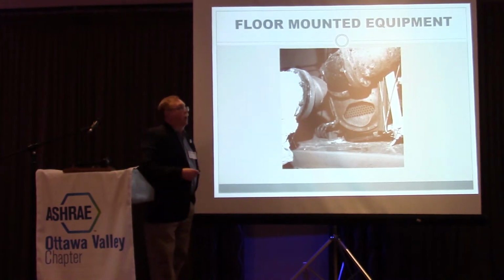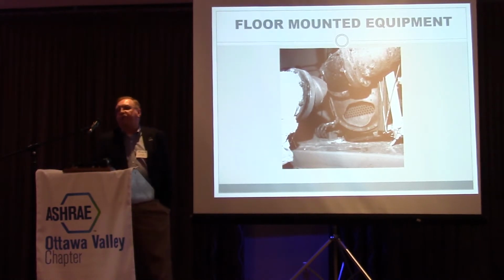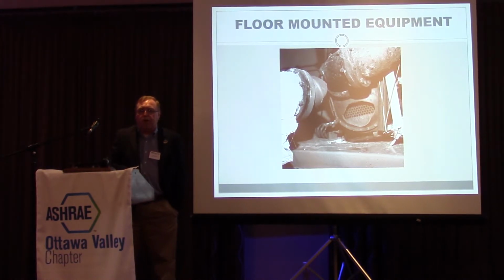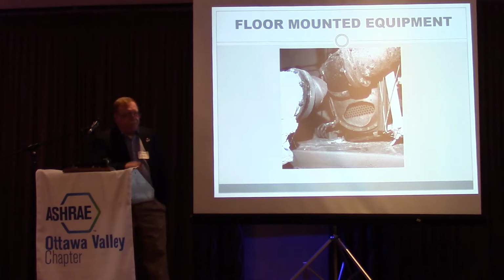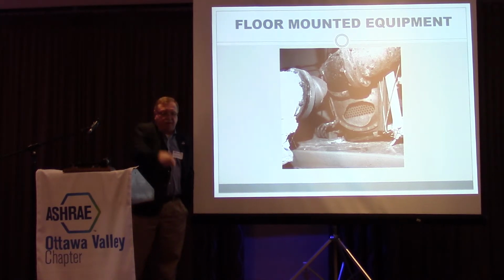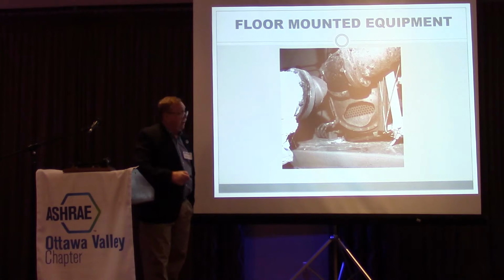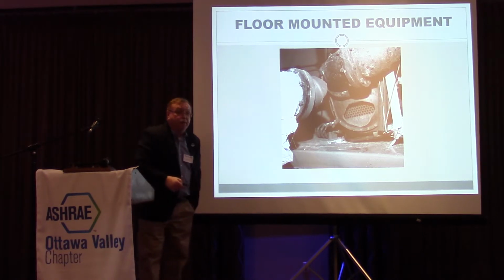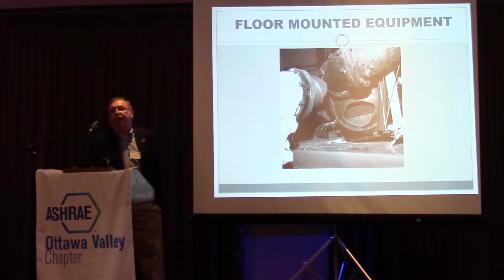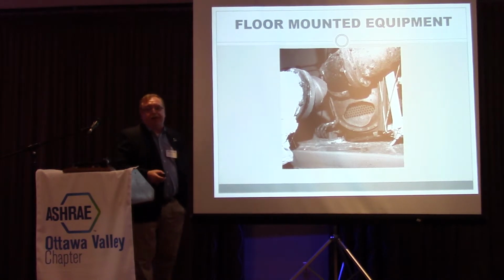The building codes require that you have a certain amount of movement based on the lateral drift between the two floors of wherever you are in the United States. So if this floor is going to move an inch compared to that one, in the United States you've got to have a minimum of an inch of movement. That means you've got to have a flex connector that can do that.